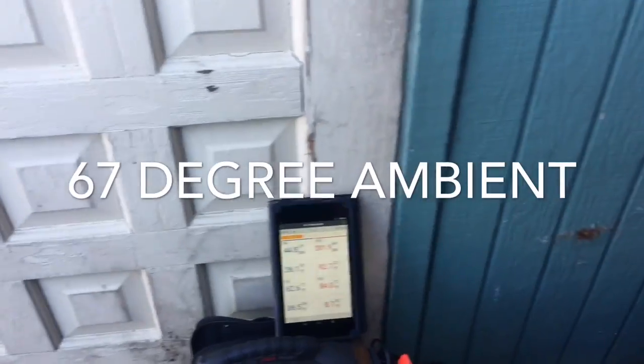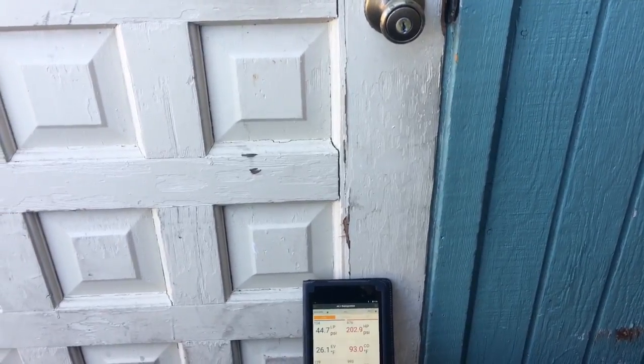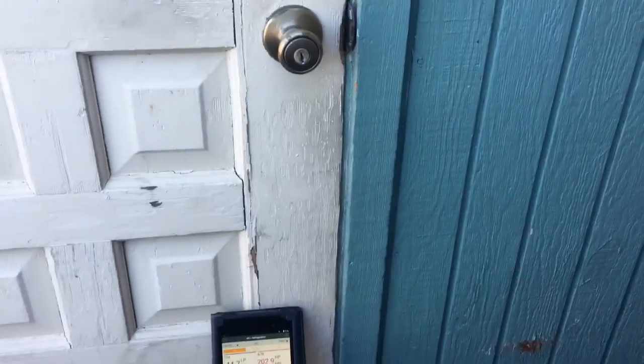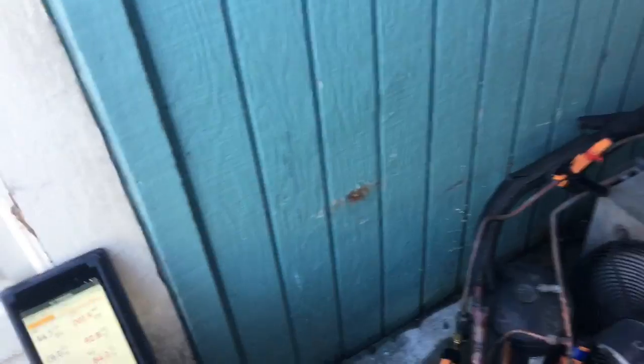I wish I could live with all those readings. I'd like to see that evaporator temperature come down, but I know that box is 50 degrees. The coil was plugged up to the max — had to wash it out. Someone had stepped on the doghouse.